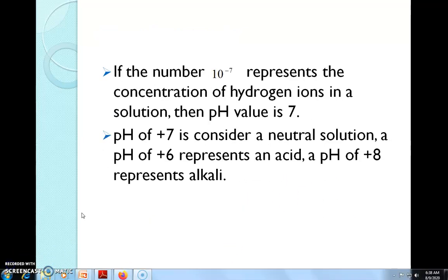Electrochemical pH determination utilizes the difference in potential occurring between solutions of different pH separated by a special glass membrane. Basically, if the pH of one of the solutions is kept constant, the potential varies in accordance with the pH of the other solution, so the system can be used to determine pH. In our analysis, the device used to effect these measurements for electrochemical pH determination is the glass electrode.